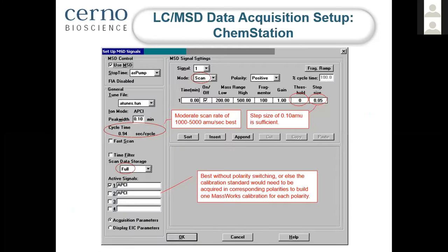For LCMSD, if you're running LCMSD under ChemStation software, here's the setup page. The data acquisition mode is called scan. So it's a different terminology, sometimes may be a little confusing at the beginning, but you'll get used to it. So the scan mode has to be set to scan, which means the profile data. And the scan data storage has to be turned on to full storage as well, in addition to changing the acquisition mode. And the threshold needs to be set to zero.